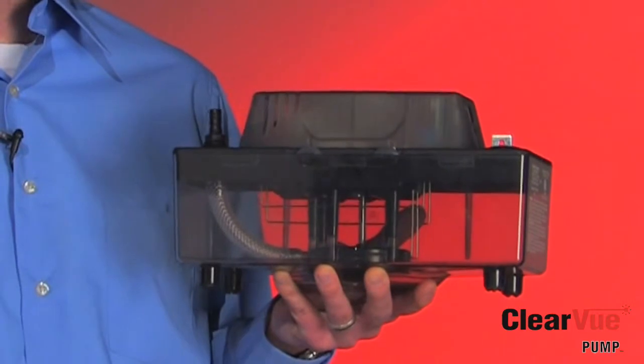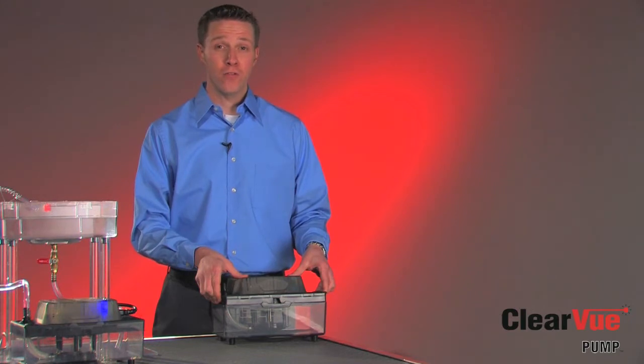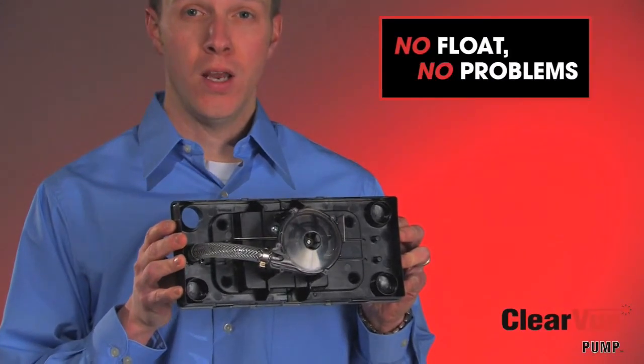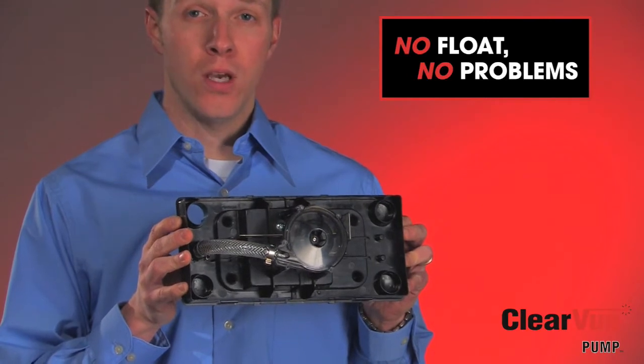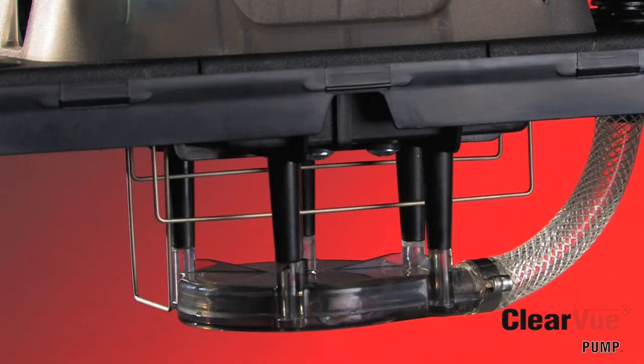But that's not close to the most important feature of this pump. What we've done with ClearVue is we have removed the float. The float is one of the most common sources of mechanical problems in condensate pumps in today's market. What we've replaced the float with is what we call our floatless sensor technology. Floatless sensor technology in ClearVue includes three different stainless steel sensors: the empty sensor, the run sensor, and the high-level alarm sensor. These sensors run the length of the pump so that you don't have to install the pump perfectly level. With ClearVue, it's no float, no problem.